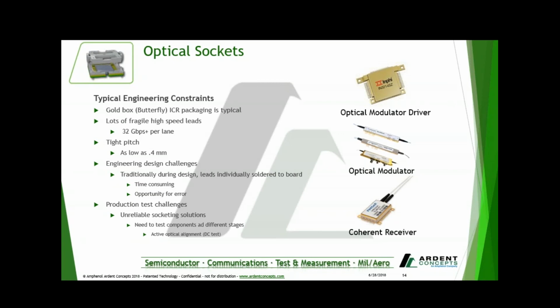In this case, the constraints they're facing are in something like a gold box ICR package, or a butterfly package, which you might find there on the top right, for an optical modulator driver or even a coherent receiver. Those leads are very fragile when they go to test those devices. So they're looking for a way to test a lot of high-speed lanes in a simple package and in a way that doesn't damage the device. Oftentimes they're also facing a very, very tight pitch, down to 0.4 millimeters.